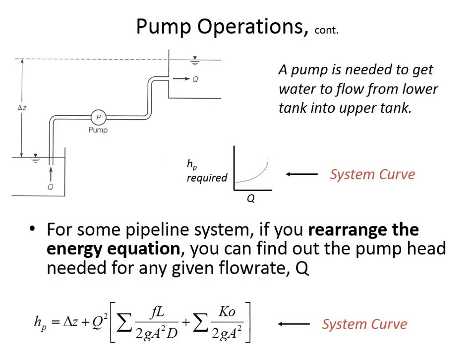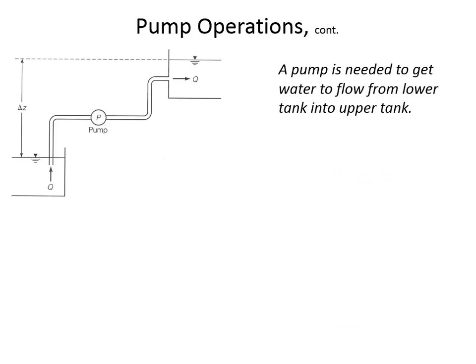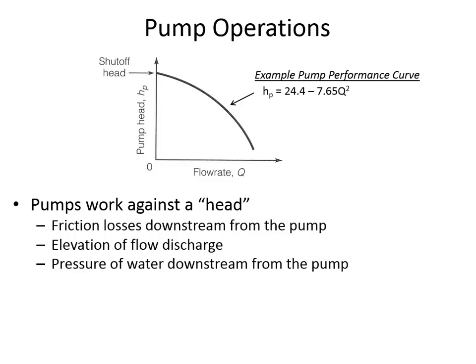So I just wanted to emphasize that in each of those homework problems, maybe they're not telling you specifically what the system curve is because you're having to interpret the drawing and create your own system curve. And in one instance, they don't tell you the pump curve. Instead of being given an equation like that, instead of being given the formula, they give you a curve.